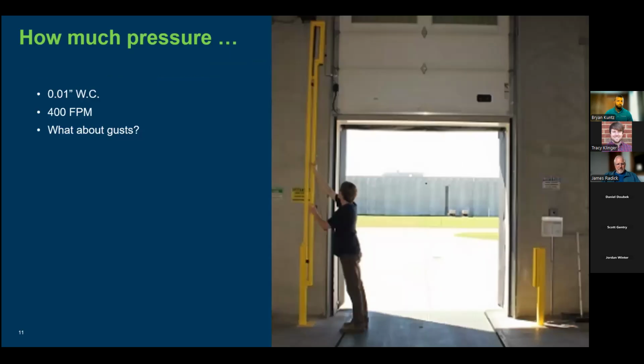And Brian, okay, how much pressure? We're only talking about a hundredths of an inch water column. That is so minute that the second bullet point there talks about 400 feet per minute. Well, what's that equate to? That's what you would have if you have a building that's pressurized to a hundredths of an inch water column.